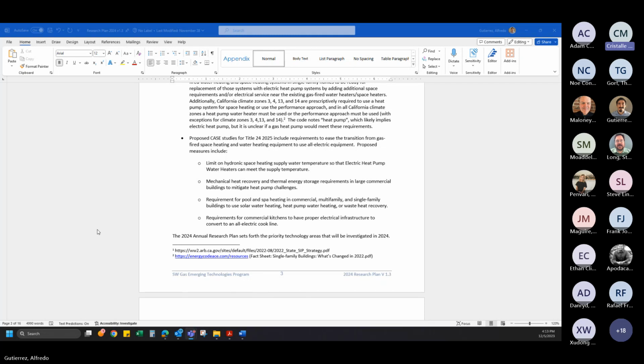For example, a limit on hydronic space heating supply water temperature—typically that might be 160 to 180 degrees Fahrenheit. An electric heat pump water heater has difficulty meeting those temperatures, if it can do it at all, so they're proposing to limit that temperature to around 130 or 140.